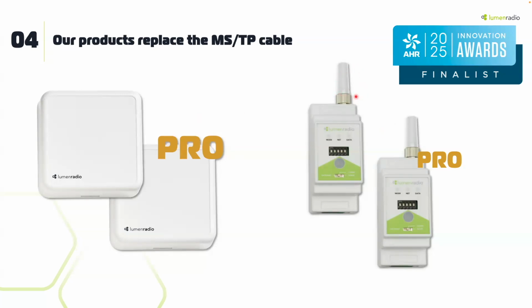So when you need to get a signal out of an electric cabinet, because metal is the enemy of wireless, you need a DIN rail unit where you can replace the antenna and put it outside the cabinet. Both of these units can be used as gateways, as nodes, and as repeaters. The Pro version is for the node side, when you have more than one BACnet MSTP device next to each other and want to daisy chain them - you can have 4 BACnet MSTP devices daisy chained to one wireless node.